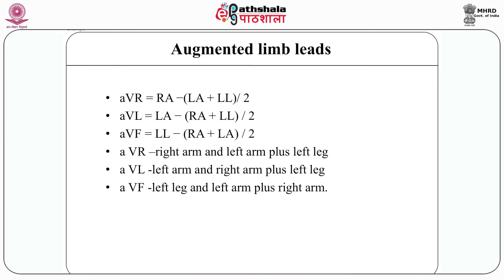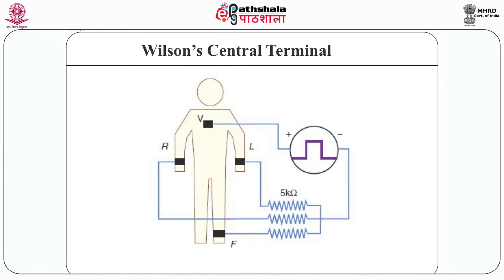Now we are going to talk about the augmented limb leads. The exploring electrode forms a positive input as: right arm electrode for AVR, left arm electrode for AVL, and left leg electrode for AVF. The reference potential for the augmented lead is formed by connecting the two limb electrodes other than the exploring electrode. AVR equals right arm minus (left arm plus lower limb) divided by 2. AVL equals left arm minus (right arm plus lower limb) divided by 2. AVF equals lower limb minus (right arm plus left arm) divided by 2.